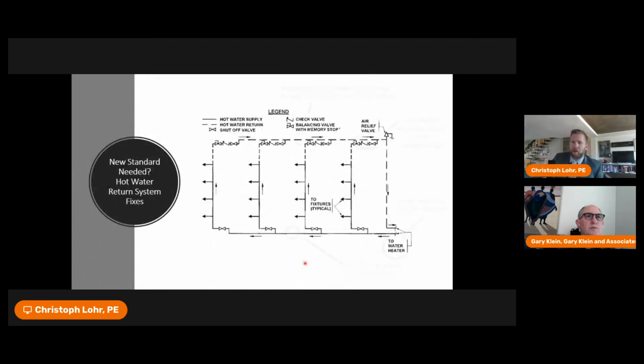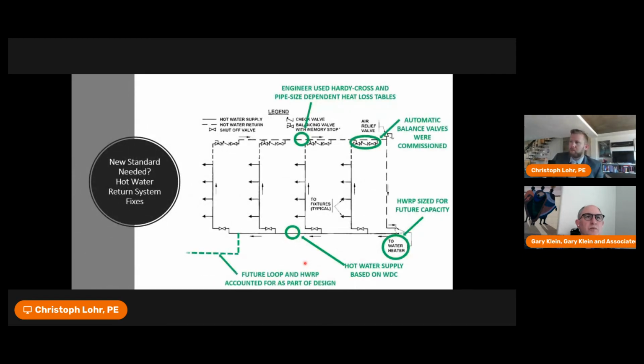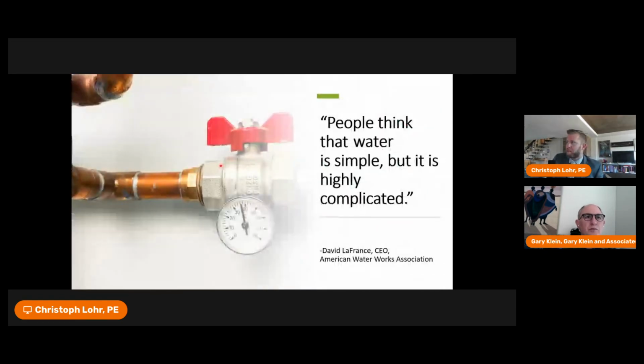So when we look at our diagram from before, again, getting automatic balancing valves that were still commissioned, to have a little bit better balancing there. A hot water return pump that's sized for future capacity, hot water supply based on the water demand calculator, an engineer that used Hardy-Cross methodology to size the pipes, and the future loop and hot water return pump were accounted for, and that they're properly located. These are all things that can fix those issues I mentioned at the beginning of my presentation.